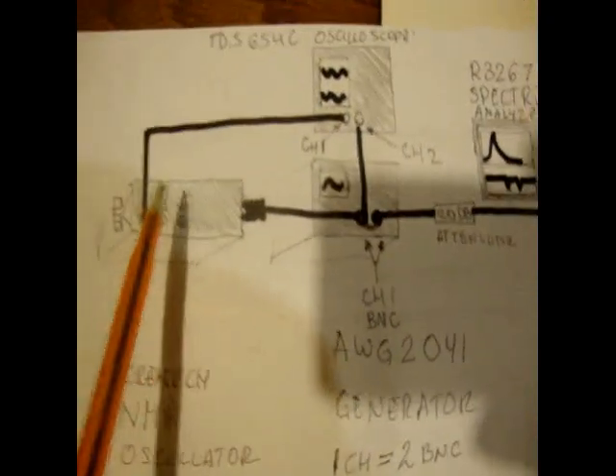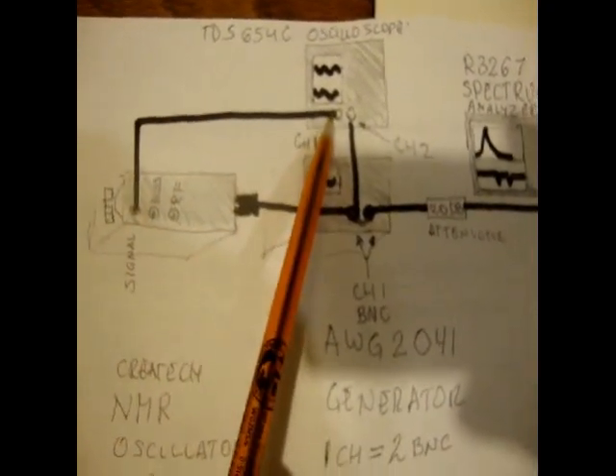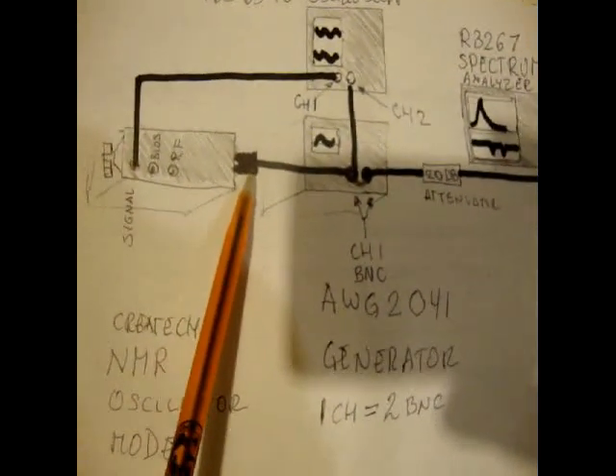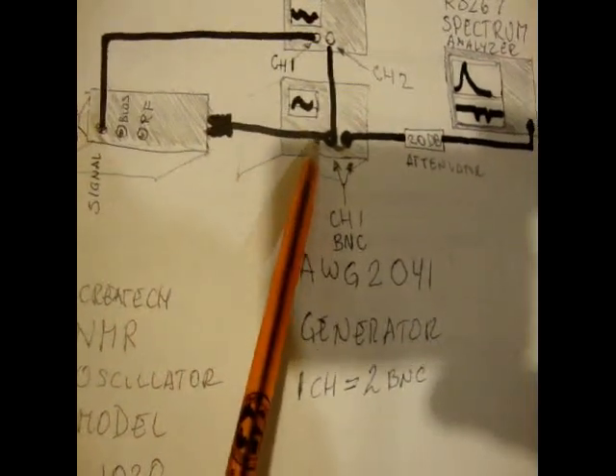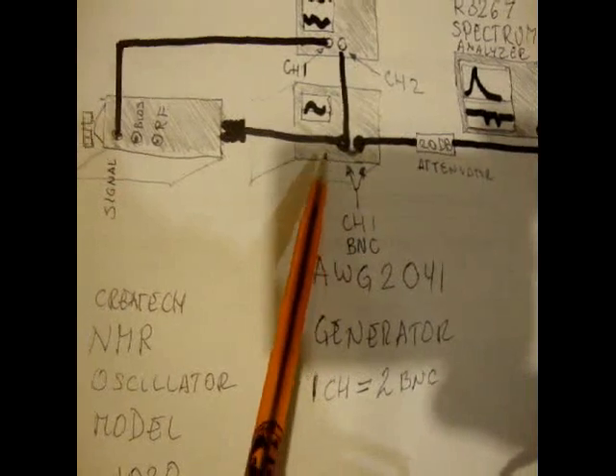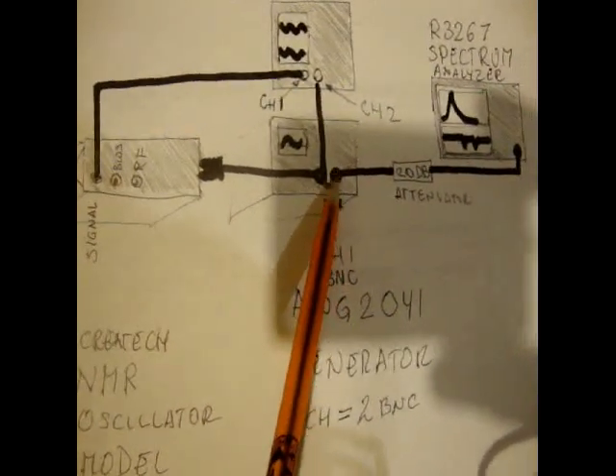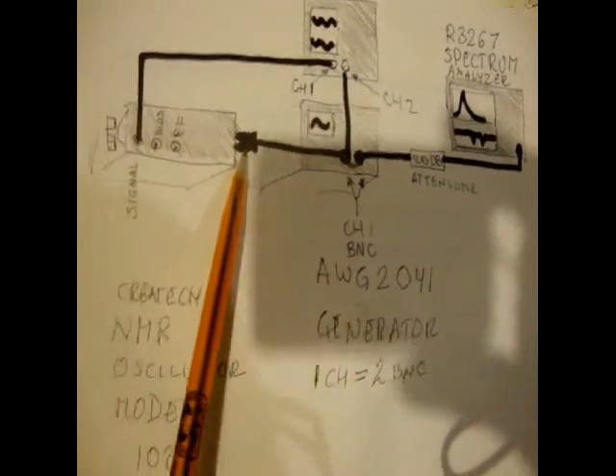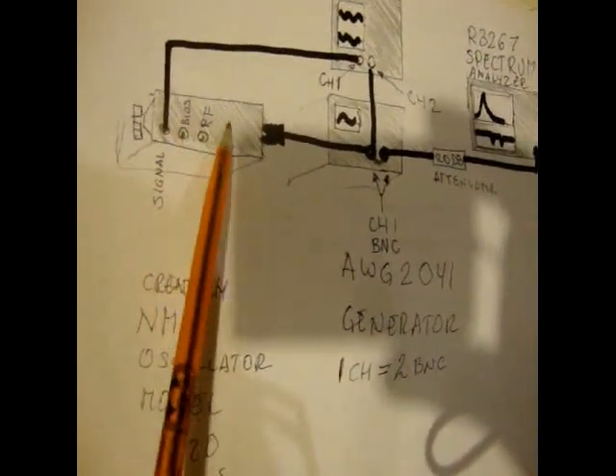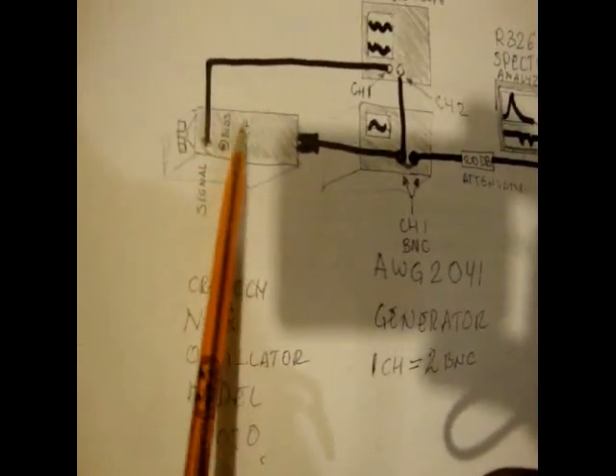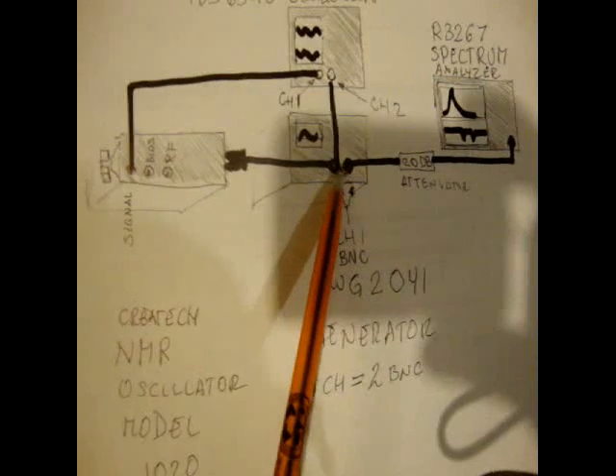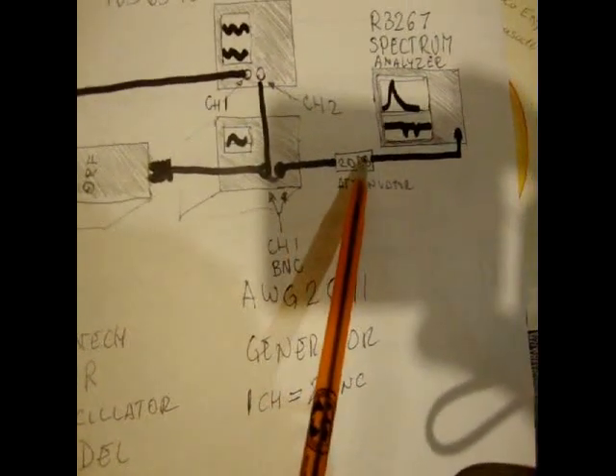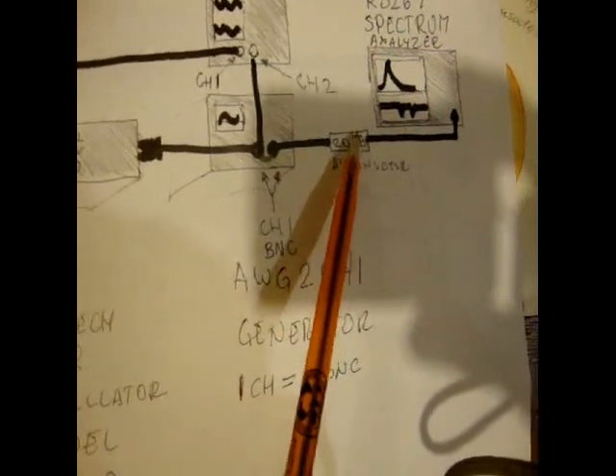Now, the output of that internal oscillator is connected to the channel one of the oscilloscope. This PL259 is an input that's supposed to come from the coil of nuclear magnetic resonance device. Now, we see that from the generator, the signal goes to the input. It looks like in here, in this device, we have a comparator that is comparing two signals. The internal oscillation and the one that is coming from here. But, look what's going on in here. From the same port, we're going through the, I have used the attenuator.